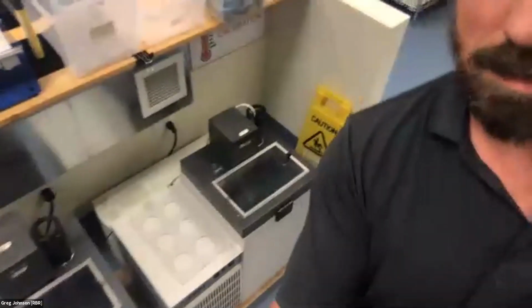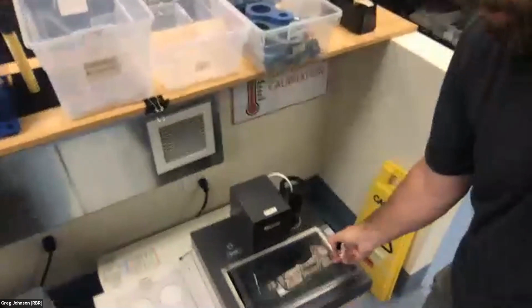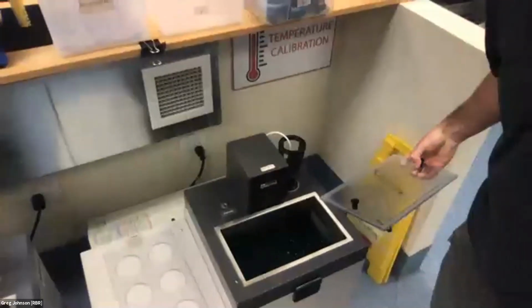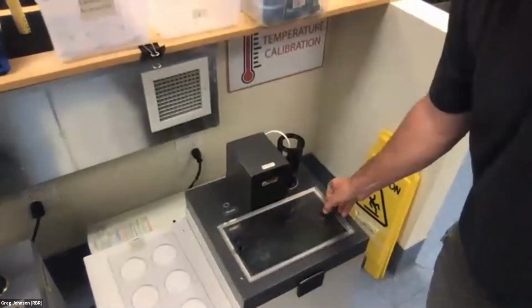Here are some of the baths that we use for temperature calibration. These are Fluke or Hart. They used to be made by a company called Hart. Now they're made by Fluke because Fluke has taken over the world. They're not yellow though, unlike most other Fluke instruments. And these are stable temperature baths. They're not particularly accurate, but they're extremely stable to better than a milli-K across the body of water they have. About 7 or 8 liters of fluid that they can manage.